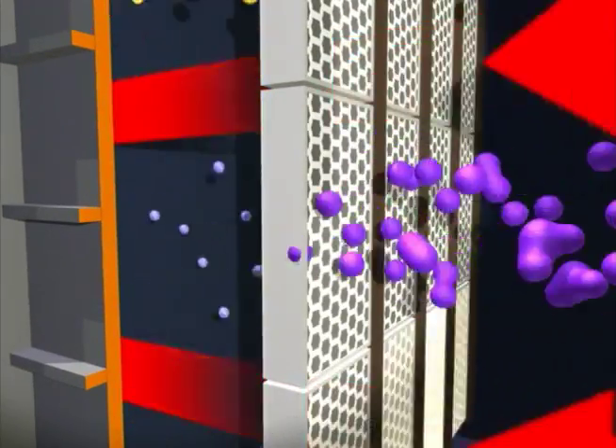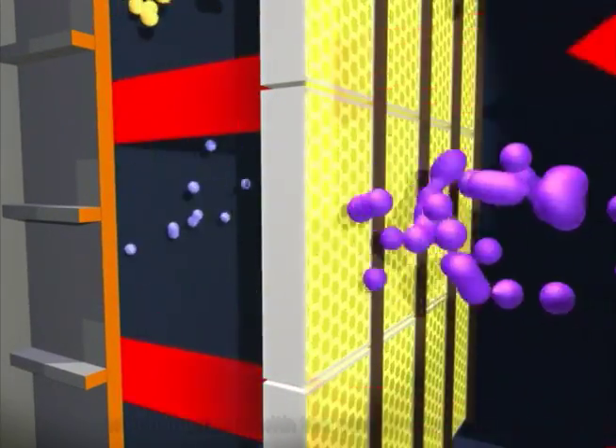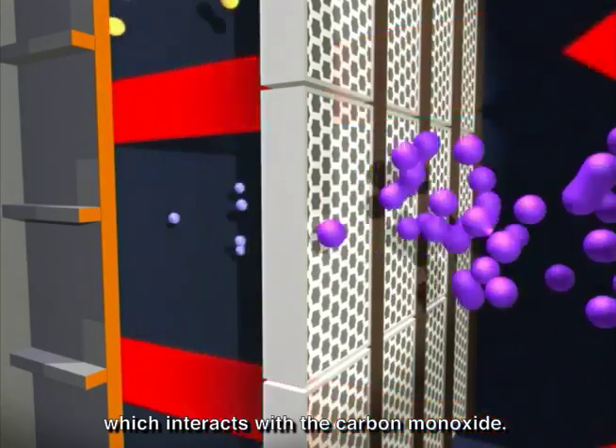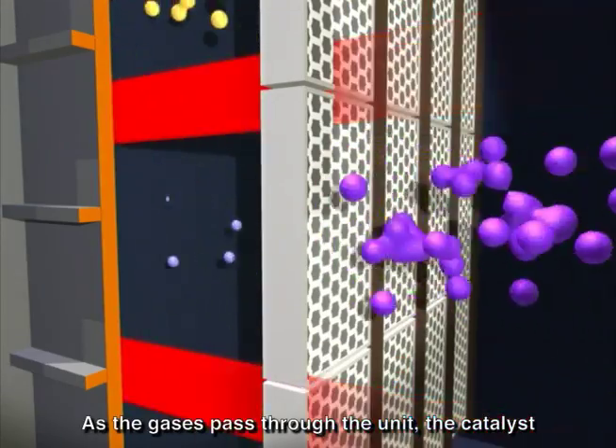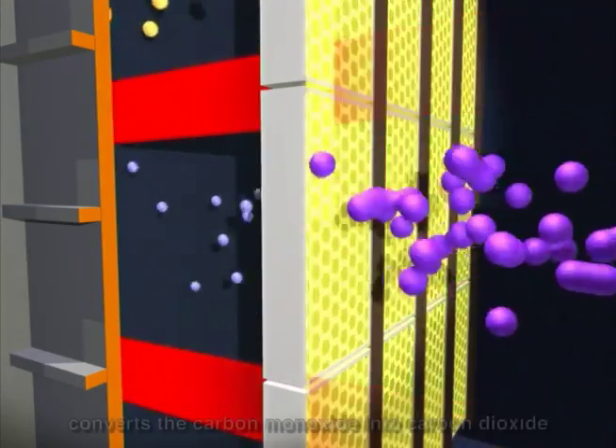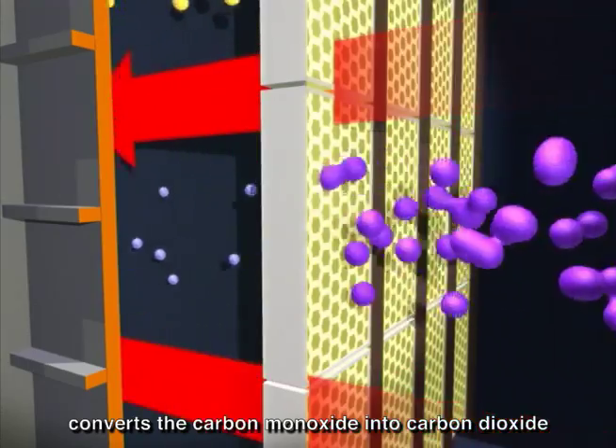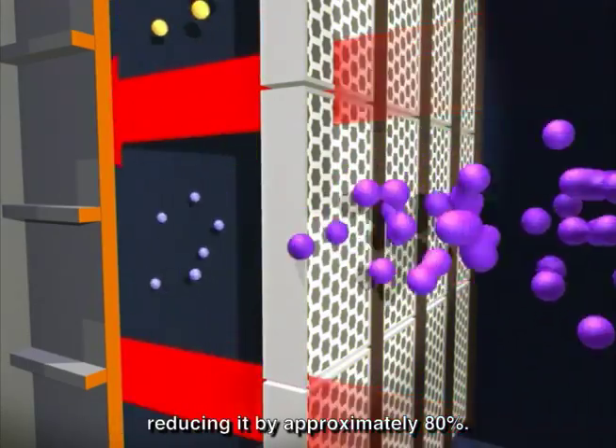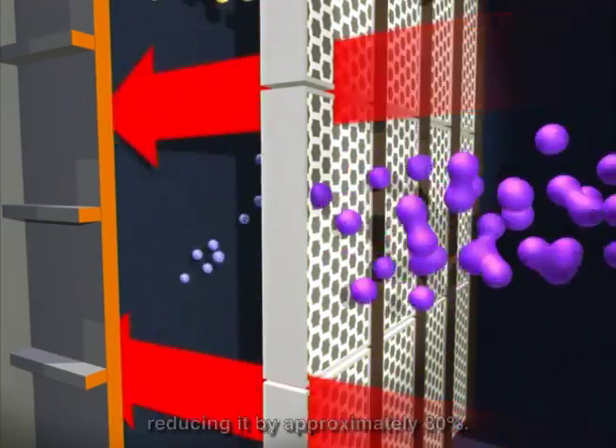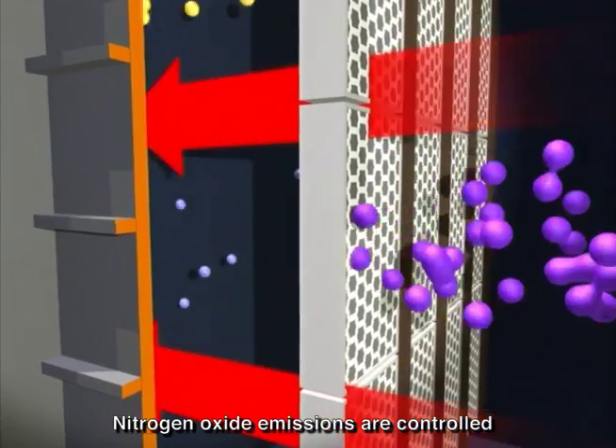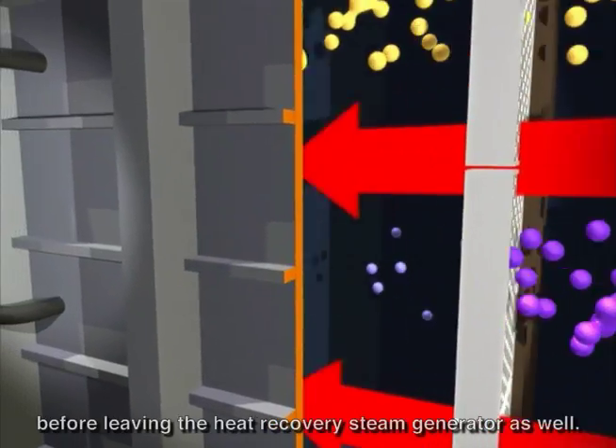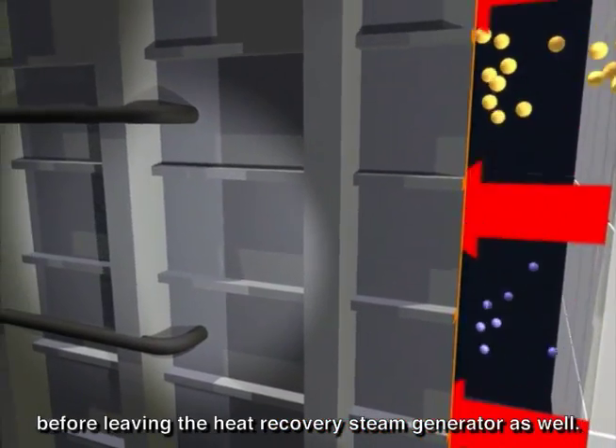The plates are coated with a chemical known as a catalyst, which interacts with the carbon monoxide. As the gases pass through the unit, the catalyst converts the carbon monoxide into carbon dioxide, reducing it by approximately 80%. Nitrogen oxide emissions are controlled before leaving the heat recovery steam generator as well.